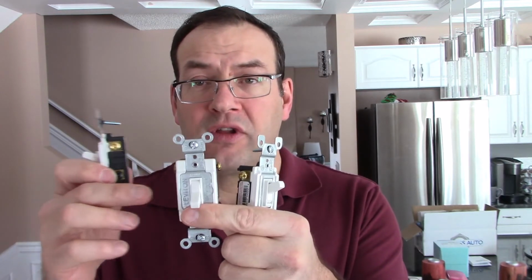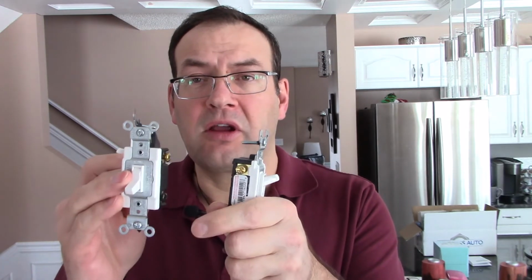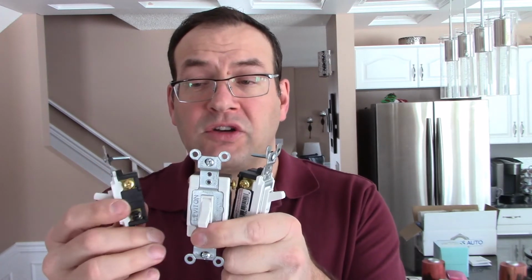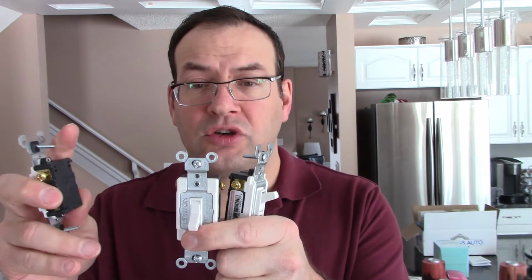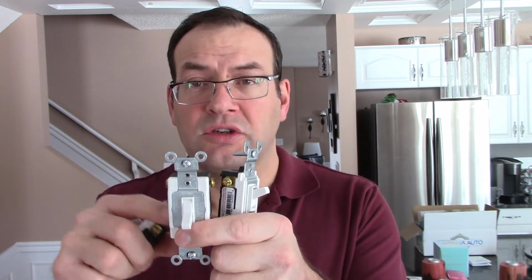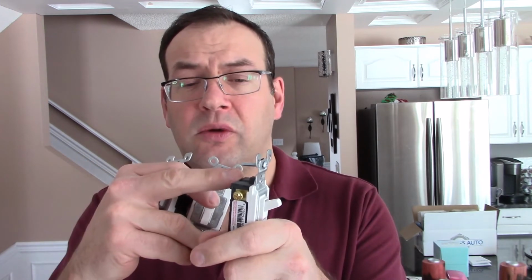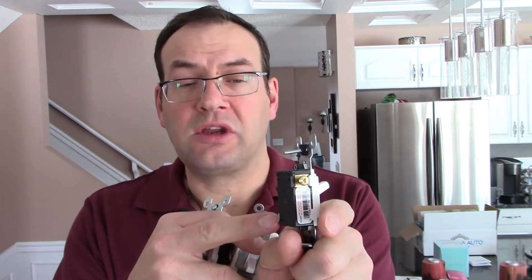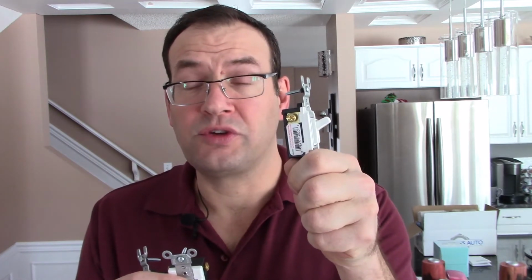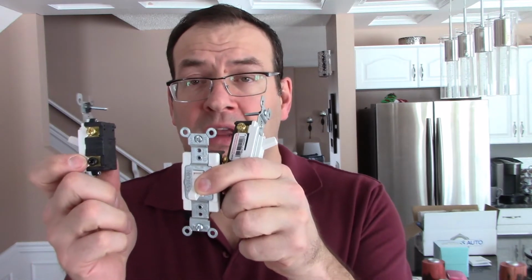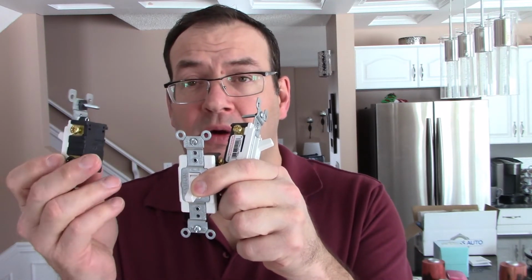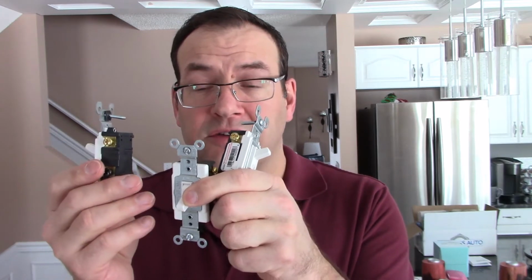Now the wiring for this gets pretty tricky. I'm not going to go into all the wiring here, but essentially the travelers from this switch go to the four-way switches from one to the next, and end up on your three-way switch, which inevitably controls your load. It'll always be the three-way switch at one end which receives power, and it'll always be the three-way switch at the other end that distributes the power to the load, to the lights, whatever it is. So that's how those all work.